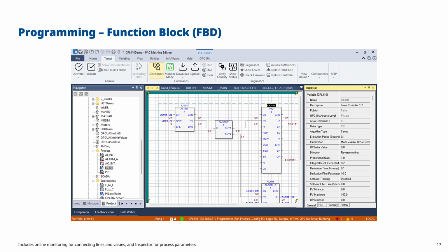Now I haven't mentioned how you create these programs yet. You do this by opening up an empty block or an existing block, and you can select and add functions in a variety of ways. When programming ladder logic, you can use the Toolchest, a separate window, and drag blocks in from there. It's also possible to enter mnemonics—for example, if you know the mnemonic for a normally open contact, NOCON, you can just type NOCON at an open location and it will insert that contact for you. Once you've got the contact or function block, you can assign variables against it.